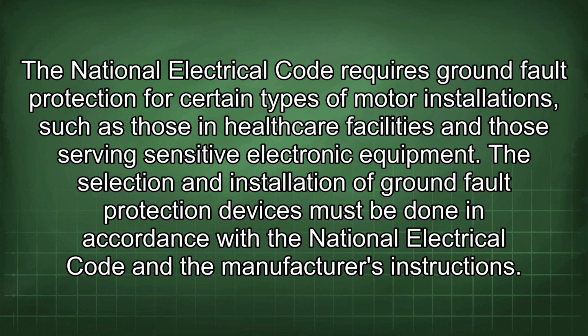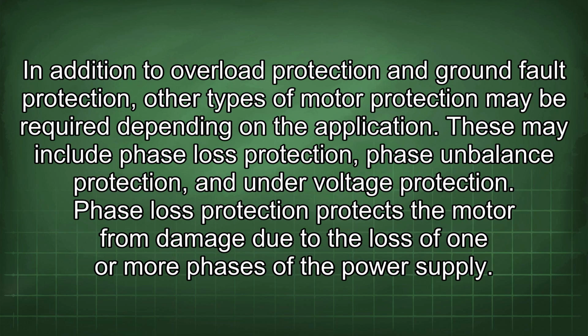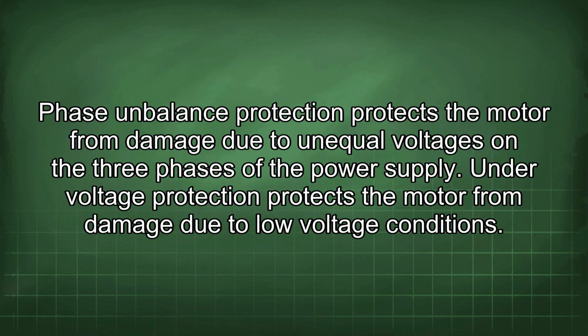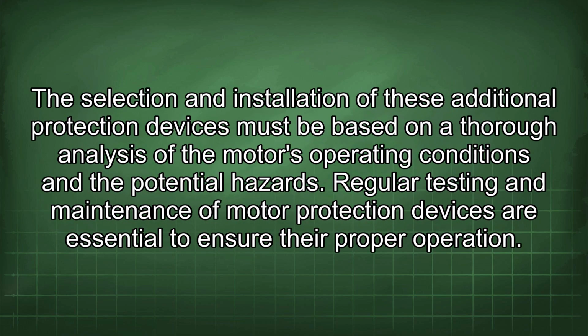In addition to overload protection and ground fault protection, other types of motor protection may be required depending on the application. These may include phase loss protection, phase imbalance protection, and undervoltage protection. Phase loss protection protects the motor from damage due to the loss of one or more phases of the power supply. Phase imbalance protection protects the motor from damage due to unequal voltages on the three phases of the power supply. Undervoltage protection protects the motor from damage due to low voltage conditions. The selection and installation of these additional protection devices must be based on a thorough analysis of the motor's operating conditions and the potential hazards.